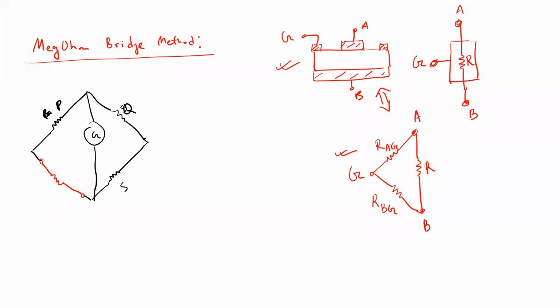So let us redraw this delta connected network over here. So this is A, B. Our goal would be to measure the volume resistance between these two terminals, and using the guard ring, we would like to make the connection in such a way so that the effect of these two leakage resistances can be eliminated.